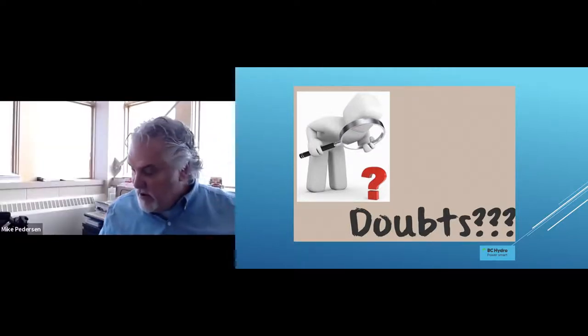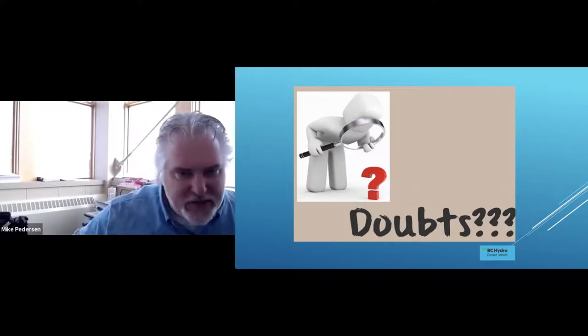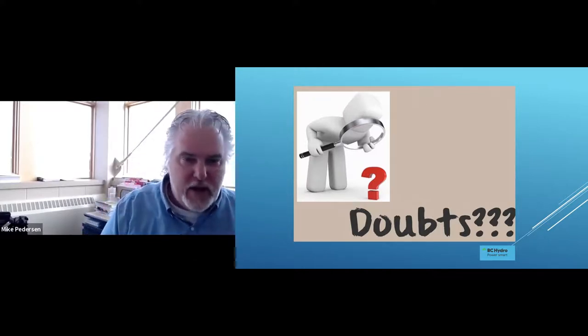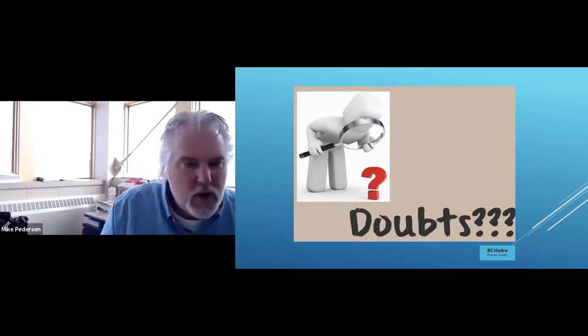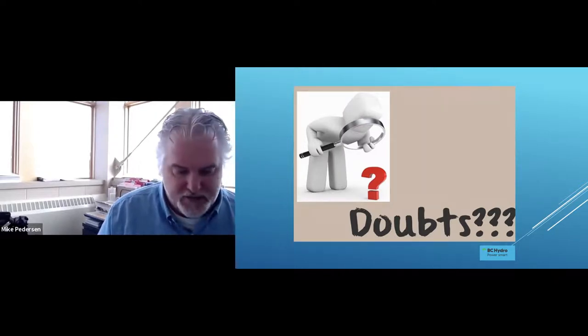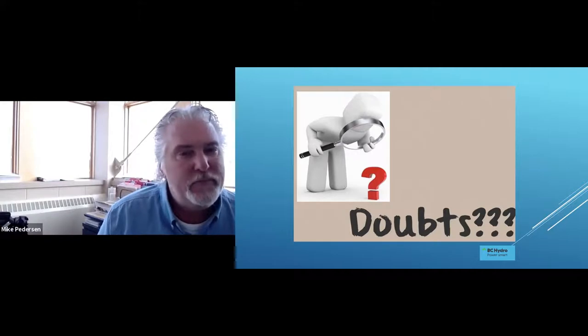Igor, thank you very much for that fine presentation. And we do have a few questions. I'll ask one now, and then I'll wait until the end of Ozren's presentation to ask some more. One question that came in is: one of the slides showed the stator winding with end winding blocking. Did this machine experience partial discharge related issues when those blockings were contaminated?